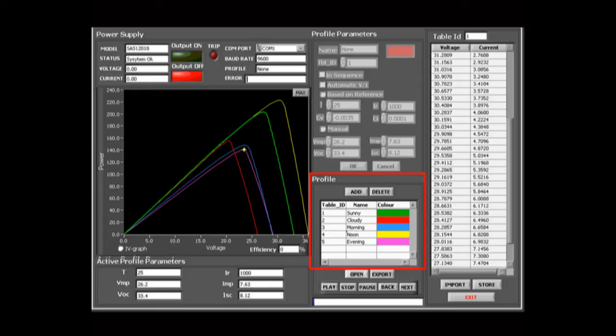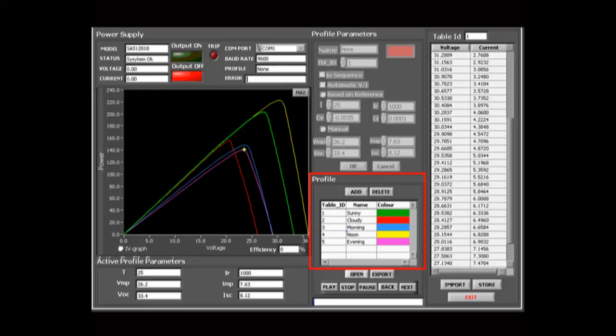In a sequence, each profile is programmable from 2 seconds to run up to 60 seconds. Each table has a unique table ID. Any of the profiles can be selected and exported to SAS to check the performance and tracking efficiency of the solar inverter or microconverter. We can create single profiles and run them separately or list them in sequence and run one after the other at specified intervals without human intervention. This facility is particularly helpful when we want to evaluate a panel performance over a day under varying environmental conditions.